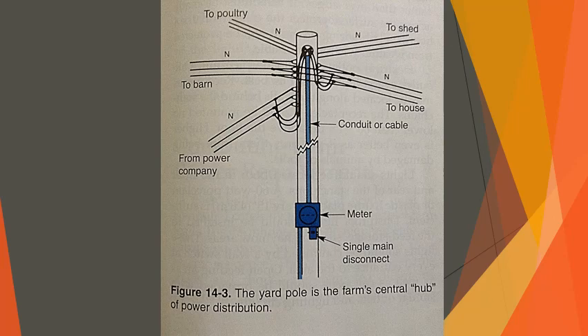The yard pole service drop. Although each building will have its own service panel containing fuses or breakers for overcurrent protection, the service drop and meter will be located at the yard pole. This will serve as a power center and overall disconnecting means for the farm. The yard pole is shown in Figure 14-3. A fire pump disconnect and emergency power transfer switch may also be located here.